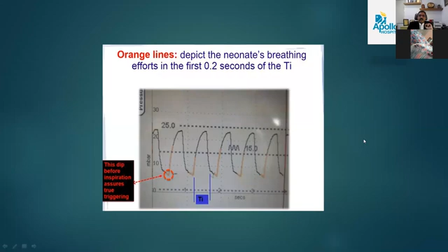So these are the different types of ventilator modes. The regular IMV, or what we call CMV, continuous mandatory ventilation or intermittent mandatory ventilation. You have to set all the things, but one major difference is that synchronization is not there in this mode. If you want, you can add the triggering in the recent ventilators which we have.